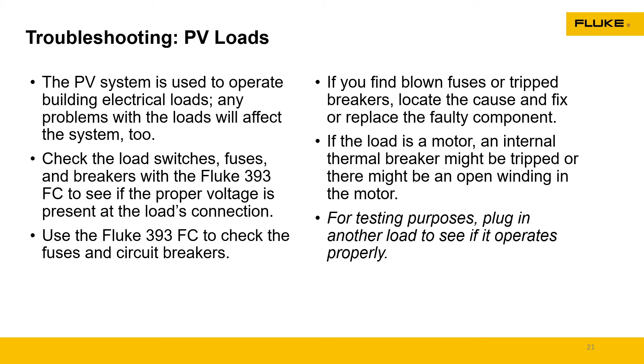And that's where you'd be using a DMM or a clamp meter or even a scope to determine what that looks like. You know, broken wires can affect that. Obviously, if you have a three-phase system, you may need to be doing some insulation testing, validating that you don't have any ground faults or shorts going to ground. That would be a good tool in this aspect.